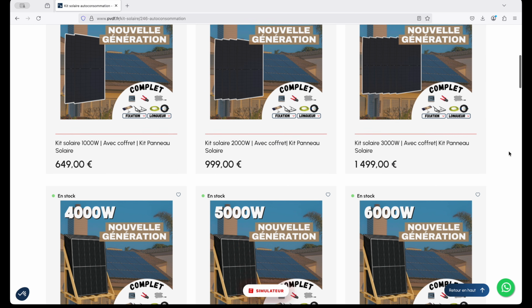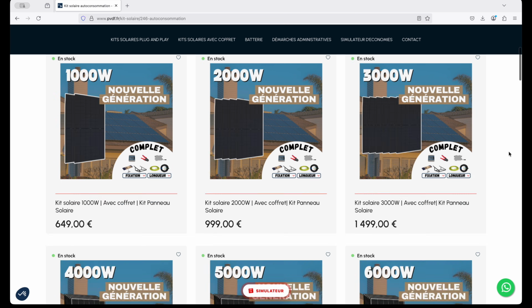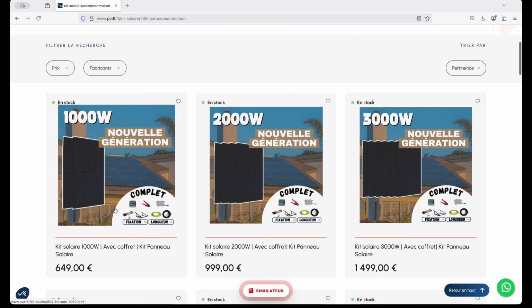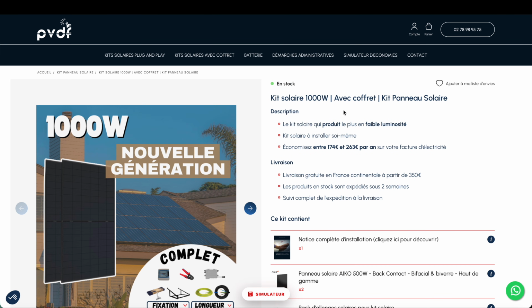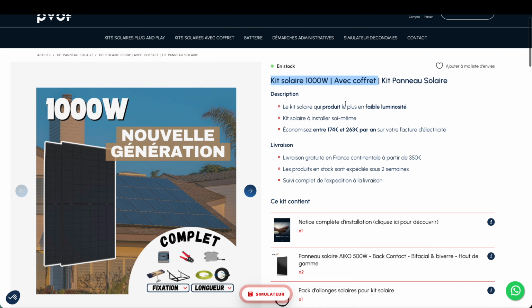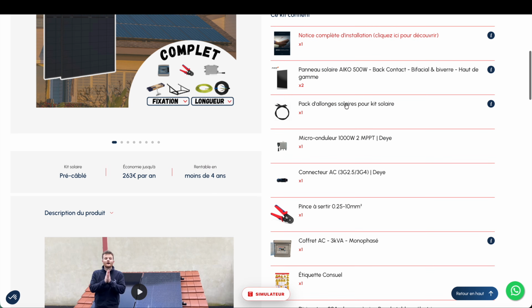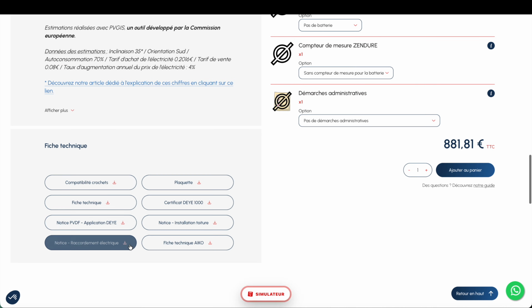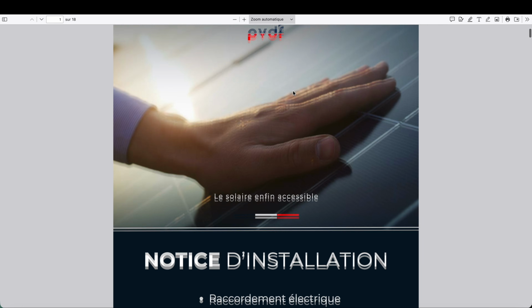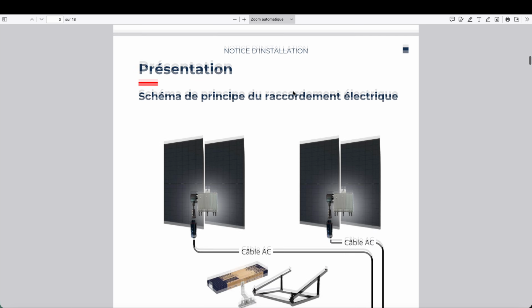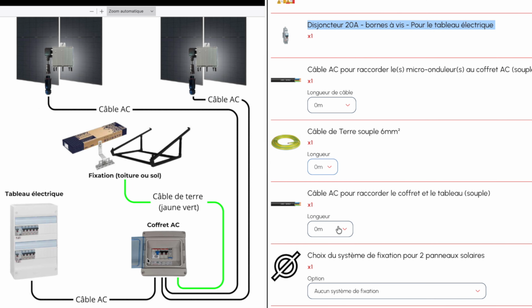In this case, you're no longer limited to 3000 watts because, unlike plug-and-play systems, the wiring is sized according to the power and cable lengths involved. This allows you to go beyond the limits of standard outlets and even install multiple systems if needed. The inverters are connected by cable to an electrical box that contains the necessary protections for the solar installation. This box is then connected to your main electrical panel through a dedicated breaker.